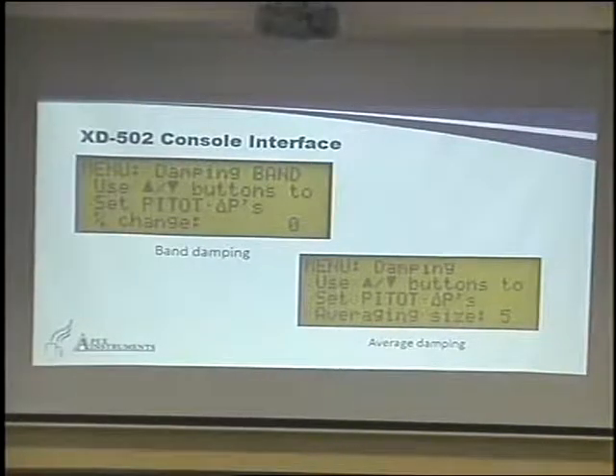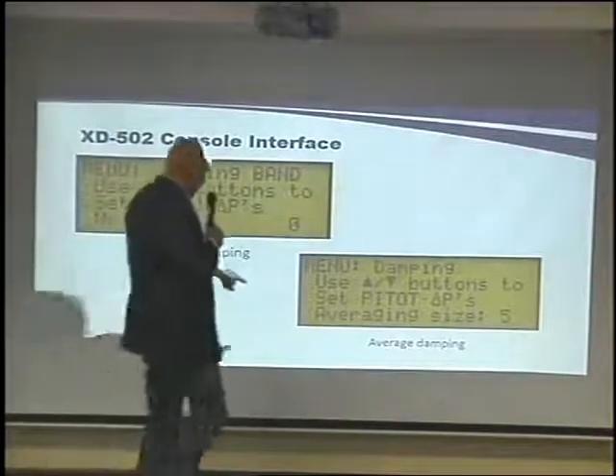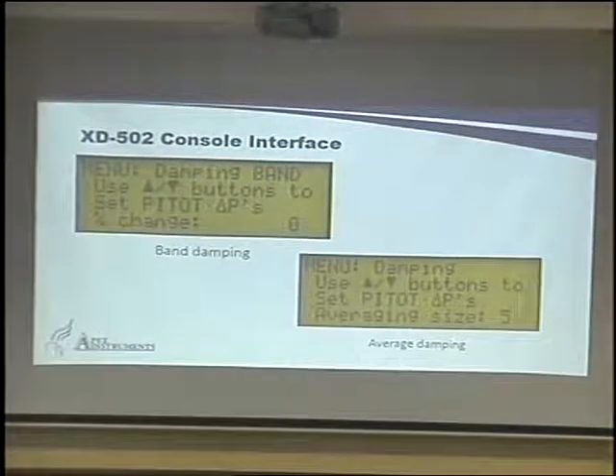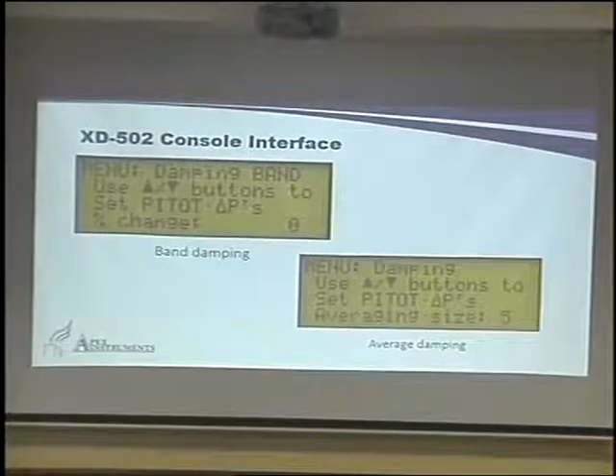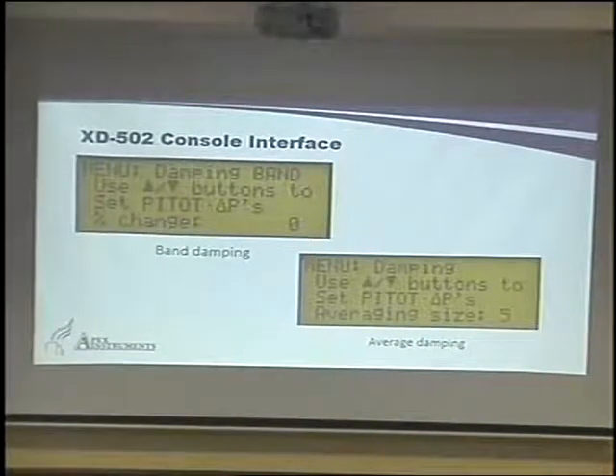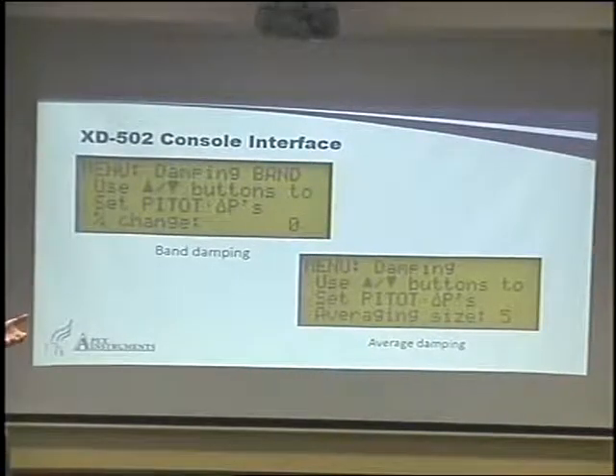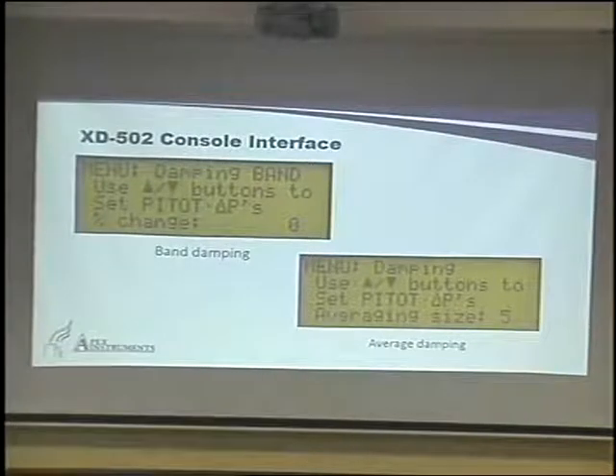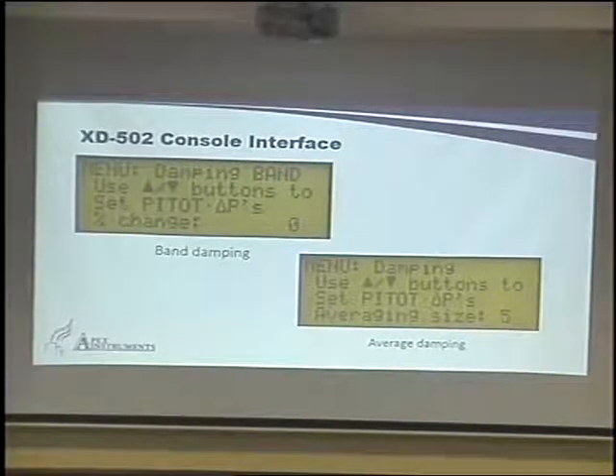So there's a facility in the software that allows you to average those values depending on how much you want to see. So if I was to put an averaging size of 4 in there, it means it's going to give me 1 second averages because I'm taking 4 readings every second. If I put averaging size of 20, obviously now I'm taking my 5-second averages, okay? So it's only going to display on me all of those averages over 5 seconds. So now I get a nice, stable delta P number that I can read and make my adjustments on, okay?